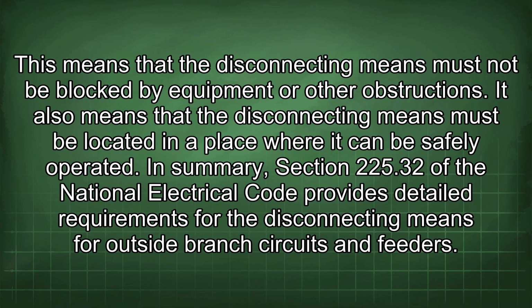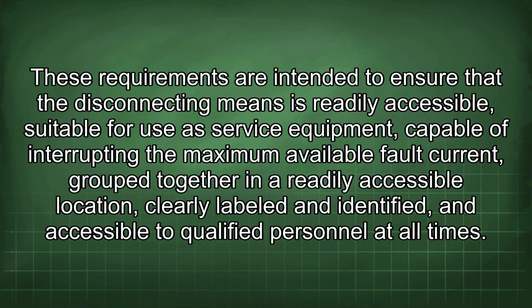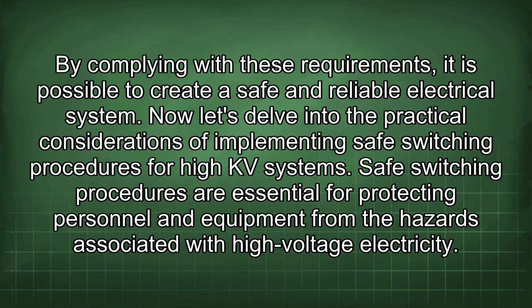In summary, Section 225.32 of the National Electrical Code provides detailed requirements for the disconnecting means for outside branch circuits and feeders. These requirements are intended to ensure that the disconnecting means is readily accessible, suitable for use as service equipment, capable of interrupting the maximum available fault current, grouped together in a readily accessible location, clearly labeled and identified, and accessible to qualified personnel at all times. By complying with these requirements, it is possible to create a safe and reliable electrical system.